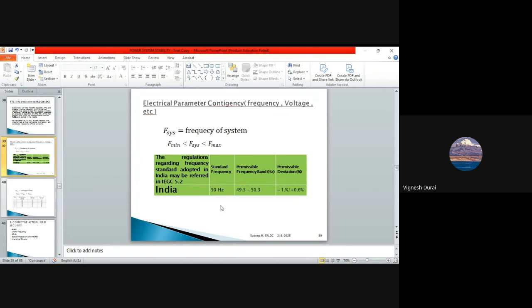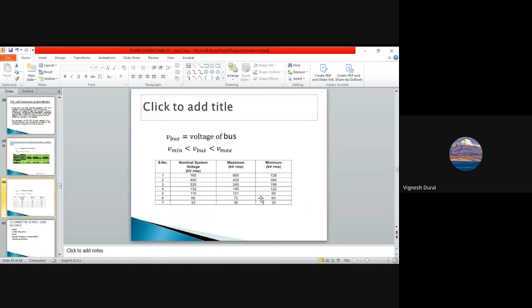For electrical parameter contingency like frequency, voltage, etc., we have the grid codes, the Indian Electricity Grid Code, where our frequency should be within a minimum of 49.5 to 50.3. Okay, we have standards. Suppose it goes below 49.5, we have to go for load shedding, or some corrective action has to be taken. Okay, this is the standard for our frequency. This is the standard for our voltage. You can see this. Bus voltage should be maintained at every bus. Suppose it is a 400 kV bus, it can be plus or minus 5%. Okay, this is a standard.